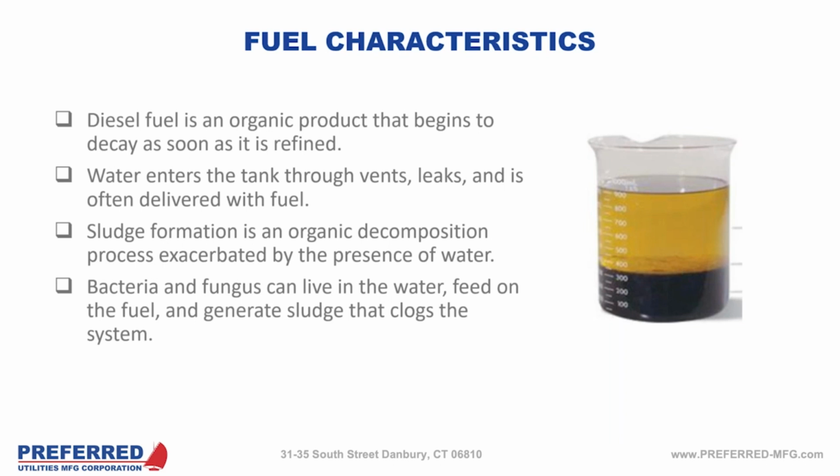So a lot of times it depends on how much fuel you are maintaining in the tank, in which the fuel and the air, as you get moisture in. For instance, if you have a 300,000 gallon tank underground, or even a 10,000 gallon tank above ground, and they are only a third full, quarter full, you have a lot of area for water to condense on those sidewalls. So I've seen everything from virtually no water in a tank that is maintained and kept clean to gallons of water in a tank, and they all present challenges.